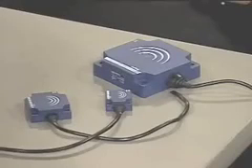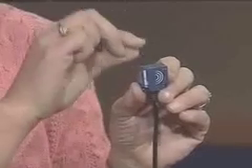Same with our inductive proximity sensors. With these, you don't have to buy a shielded or non-shielded unit — one unit will perform both functions. By pressing the teach button, you can ignore the metal behind your sensor so you can embed it in metal. You can even bring metal behind your metal target, and you can teach it a precision setting so that you can detect a small movement of a few millimeters. No one has that type of precision, and the good thing is that it's at no premium price.